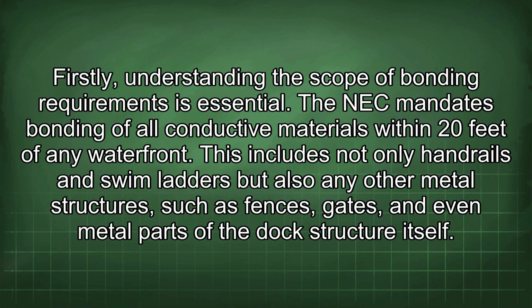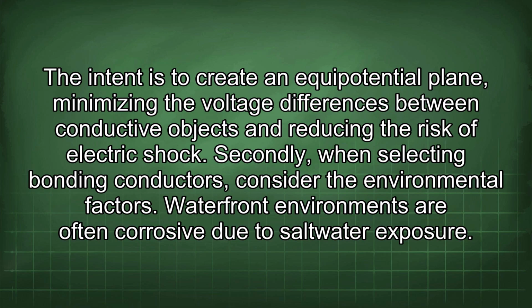Firstly, understanding the scope of bonding requirements is essential. The NEC mandates bonding of all conductive materials within 20 feet of any waterfront. This includes not only handrails and swim ladders but also any other metal structures such as fences, gates, and even metal parts of the dock structure itself. The intent is to create an equipotential plane, minimizing the voltage differences between conductive objects and reducing the risk of electric shock.